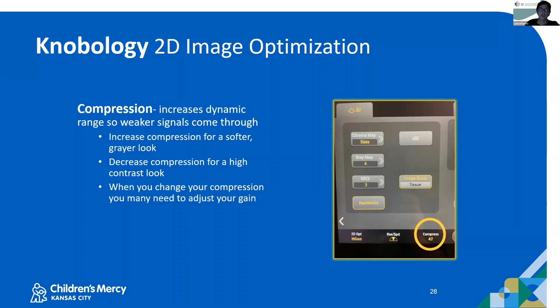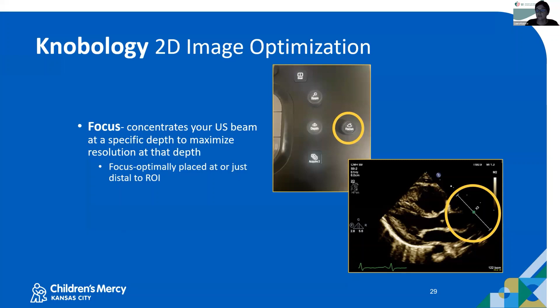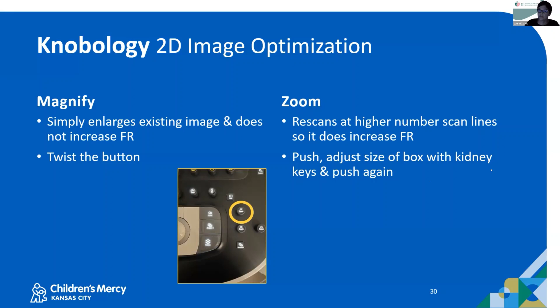The focus is a way to concentrate your ultrasound beam at a specific depth to maximize resolution there. It should be placed optimally at or just distal to the region of interest. But keep in mind, some machines don't have a focus, they autofocus, and it's not something you can change or control. You can magnify or zoom your image. Magnify simply takes whatever is in your pie and makes it bigger. Your frame rate doesn't increase. You just twist your button and there you have a little bigger image. If you want to zoom your image, you hit the button, adjust your sector size, hit the zoom button again, and then it's going to rescan with a higher number of scan lines. So you will have an increased frame rate. And it's just a way to improve resolution of something you need to look at up close.